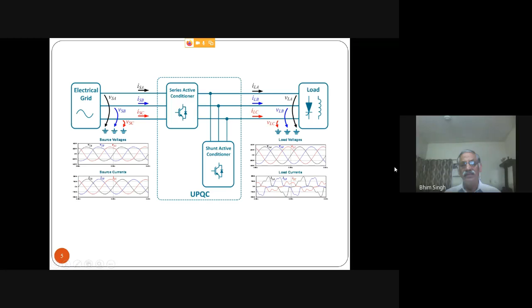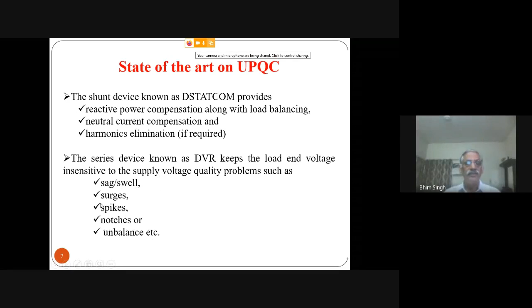Many industries are manufacturing it; this is a typical photograph from one of them. We are now able to get state-of-the-art UPQCs that can do all the tasks a D-STATCOM can do, plus what a DVR can do. The DVR can probably compensate more, not only steady state but also transient kind of compensation. Normally the shunt compensator isn't so challenging for dynamics, but the series compensator has more challenge for dynamics beyond steady state. In steady state you might have harmonics or voltage unbalance, but in addition you have transients like swells, surges, spikes, and notches.